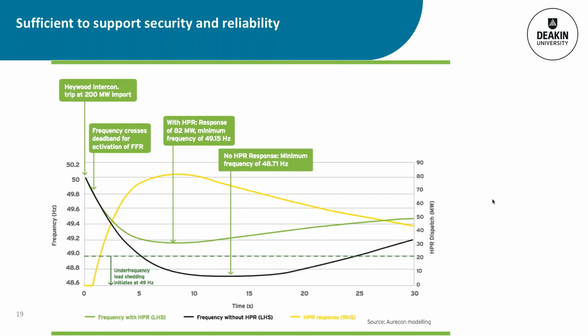Over the last year, in fact a day before the battery was officially announced, the interconnector between South Australia and Victoria failed, and the battery was asked to respond to a frequency event. The frequency controlled ancillary services market is a small market in Australia, traditionally met by gas turbines, either open cycle or steam, as they've been the fastest able to respond.